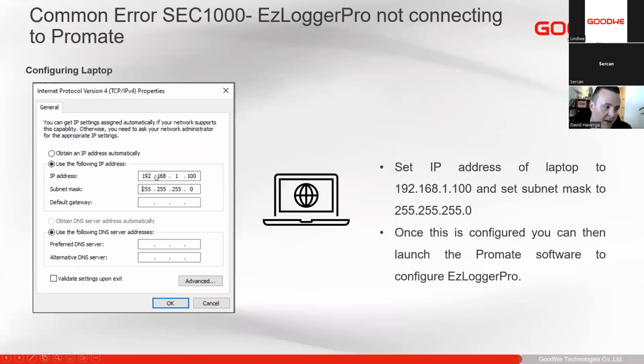So we'll set our IP address to 192.168.1.100. It can be anything up to 254 except 200. It cannot be the same as the EzLogger. It needs to be one number difference, just the last number. So you can make it 1 or 2 or 3. As long as it's not 200, it will work.